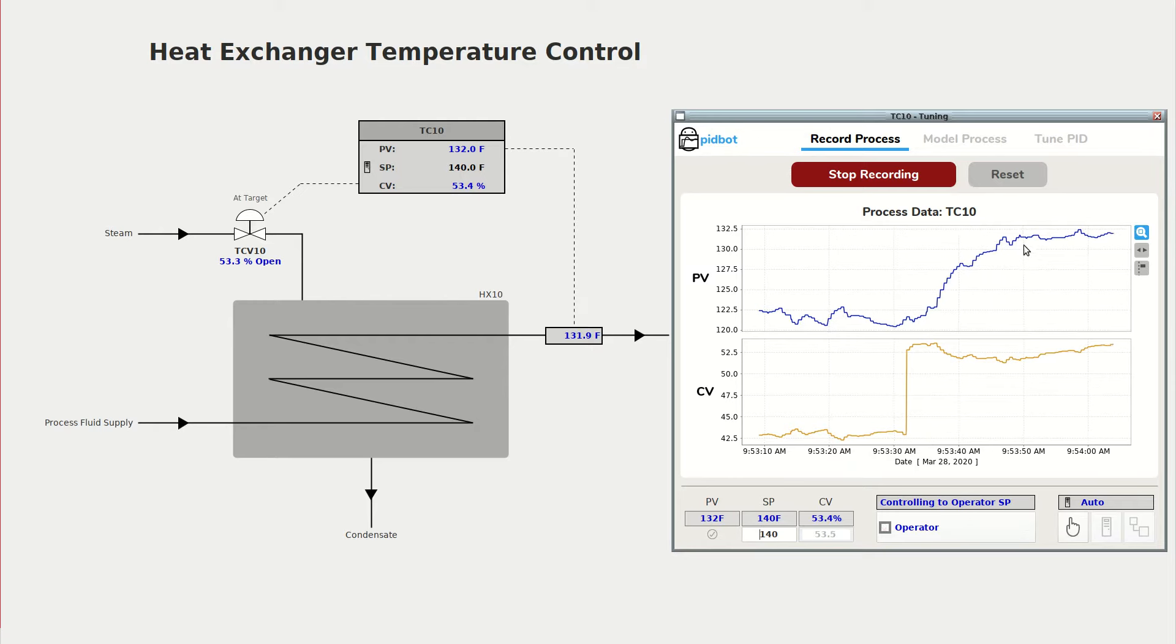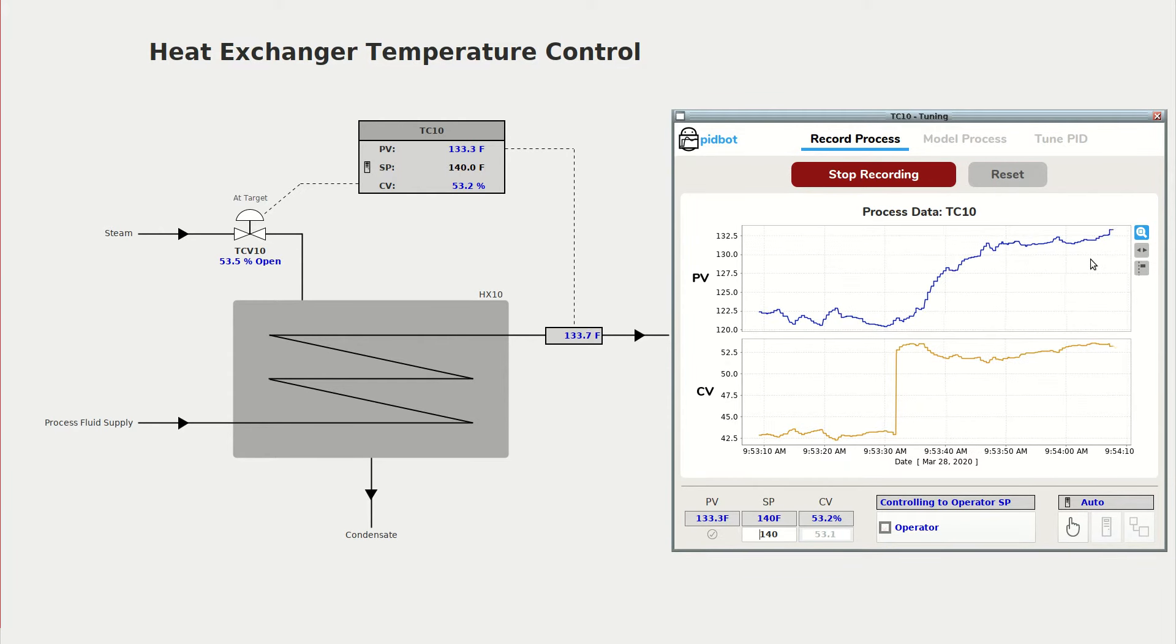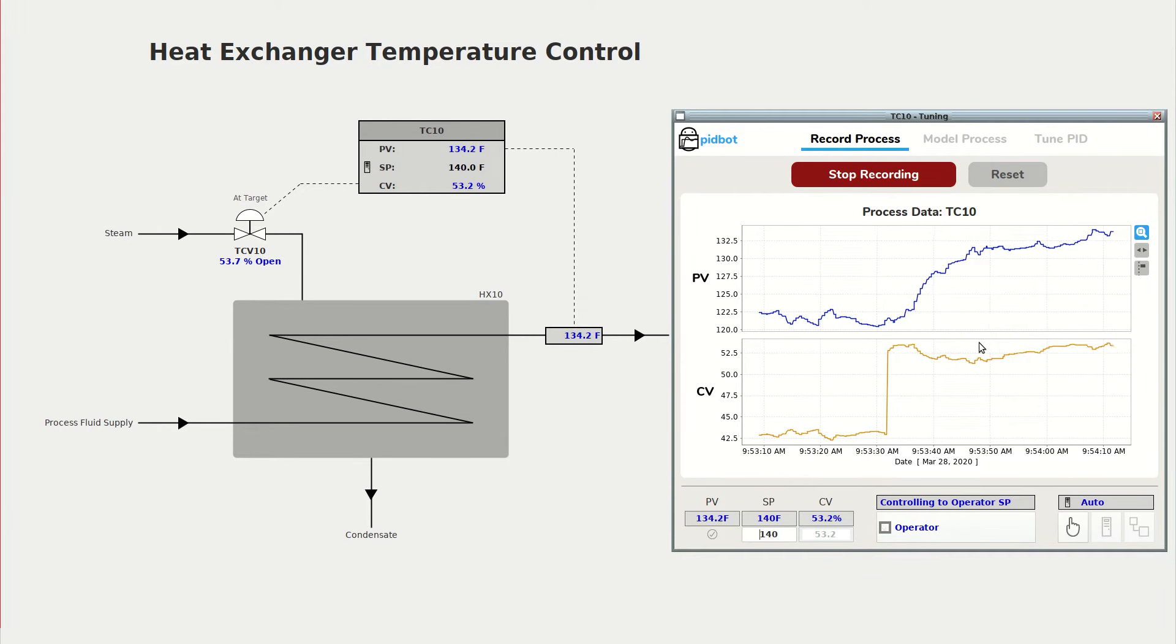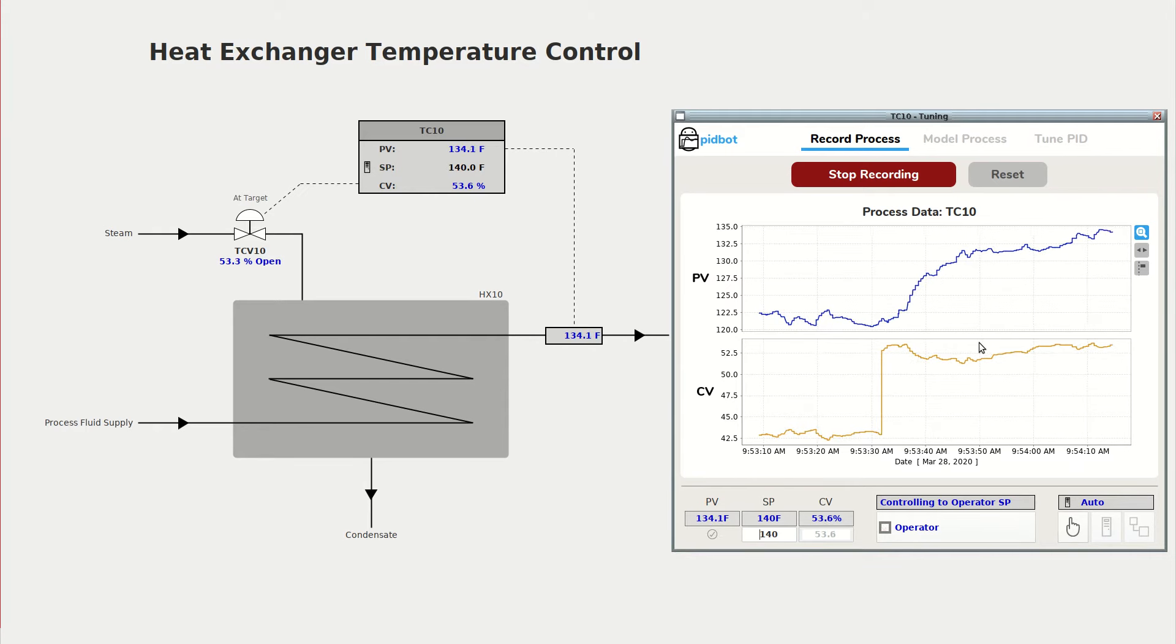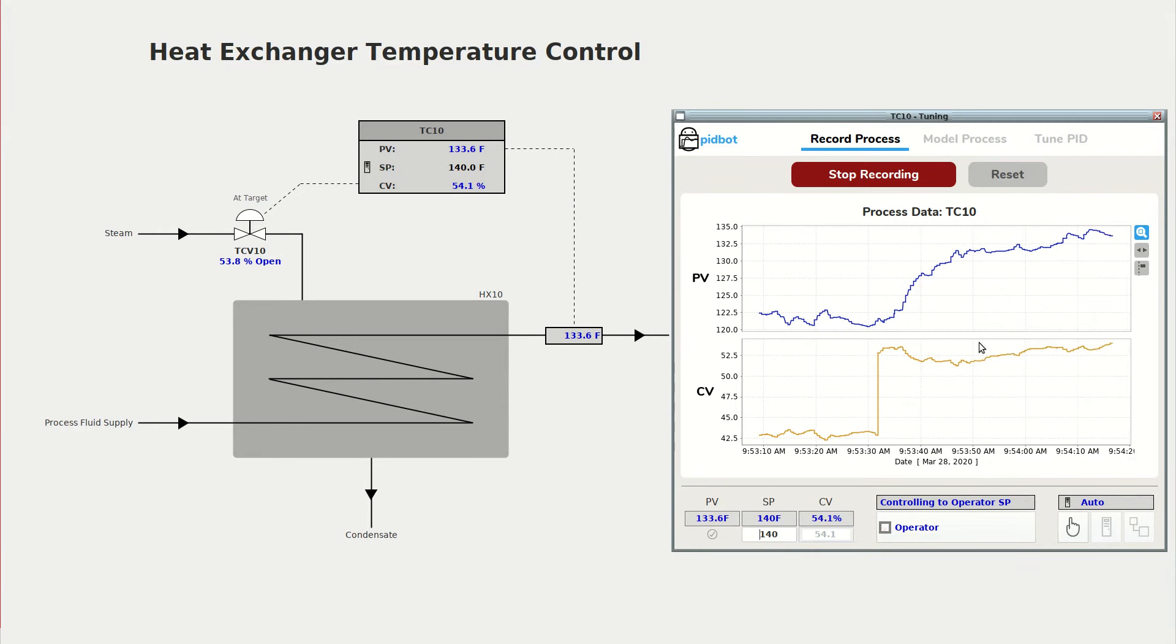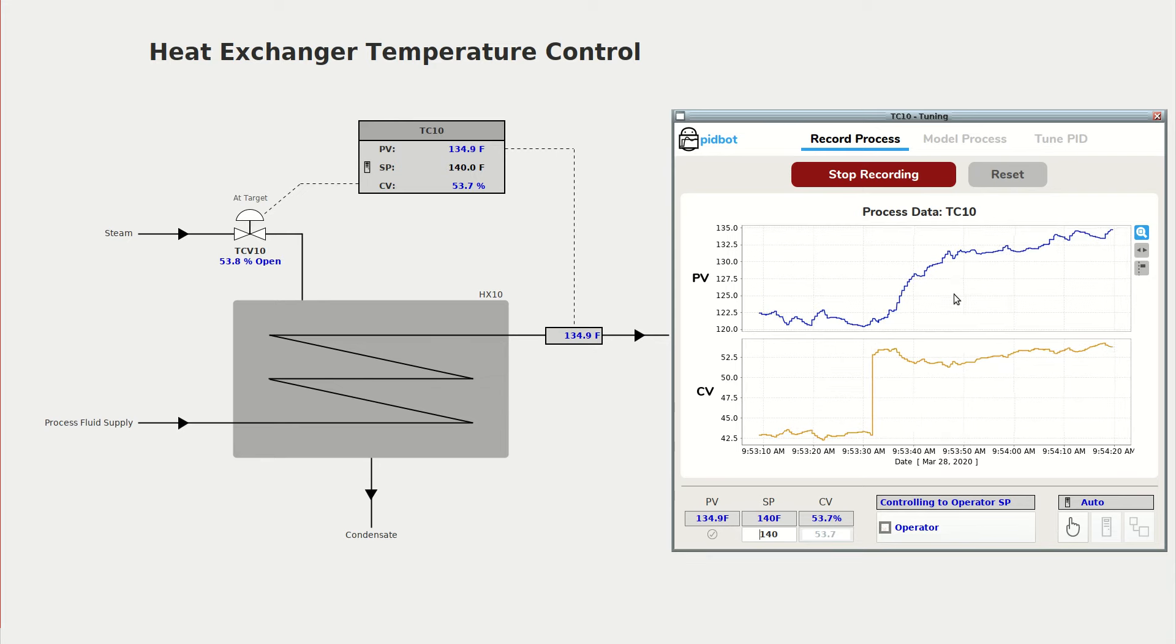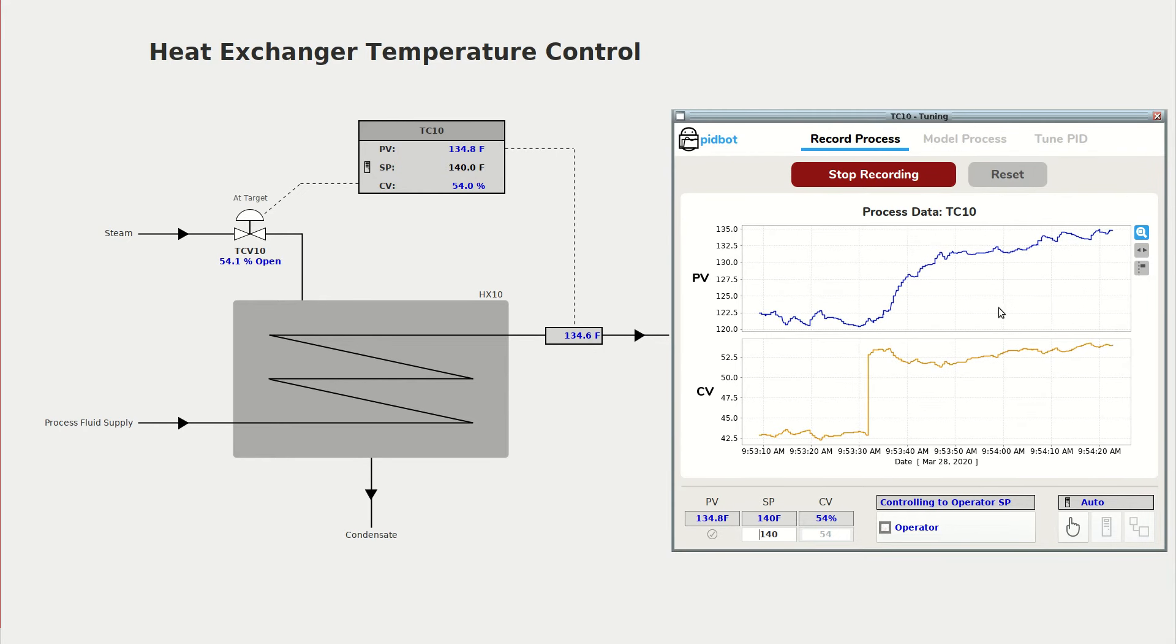The advantage to using this automatic bump test method is that you get to leave your PID controller in automatic mode, so any unforeseen disturbances while you're testing won't cause your process to go way out of the operating bounds.